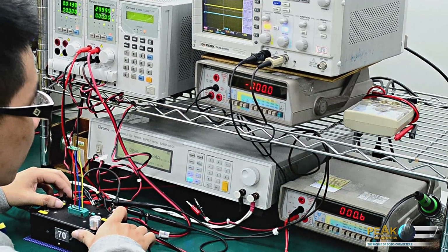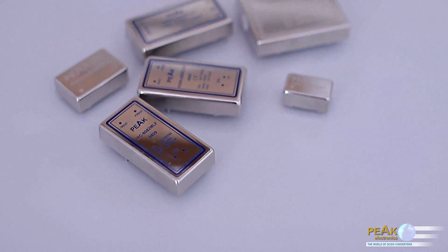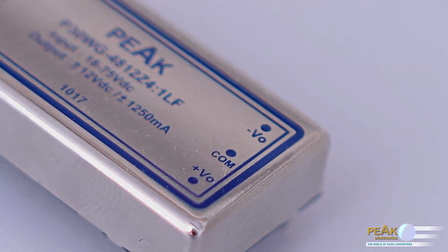An example of this: if a converter with a 12-watt output power is loaded with 0.5 amp on the plus 12 volt output with respect to 0 volt and 0 amp on the minus 12 volt output with respect to 0 volt, the plus 12 volt then drops to around 8 volt, while the minus 12 volt output rises to minus 16 volt. This means that the total of the voltages remains unchanged at 24 volts. However, the 0 volt connection has been shifted by 4 volts. Therefore, the load differences between the 12-volt outputs with respect to the 0-volt output should not be too different.